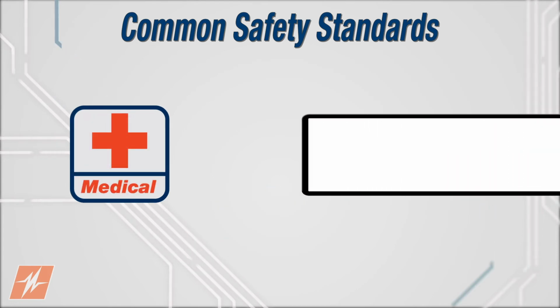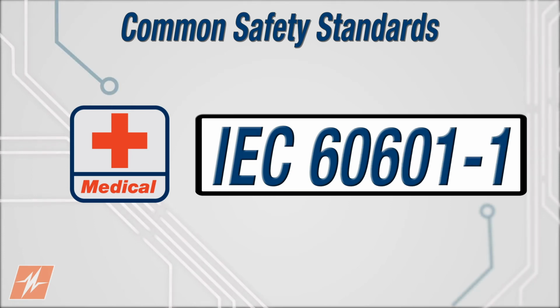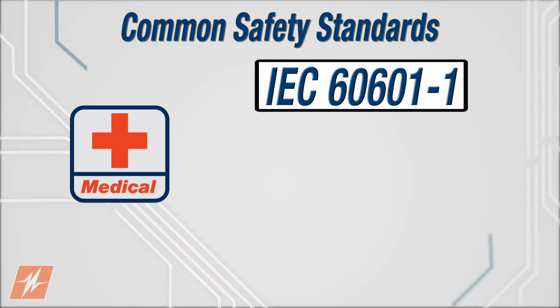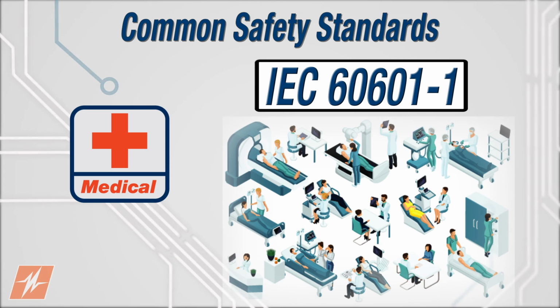The medical industry has its own safety standard called IEC 60601-1. This standard is similar to IEC 62368-1 for ICT. However, this standard has more stringent test limits pertaining to things such as leakage current and isolation levels.